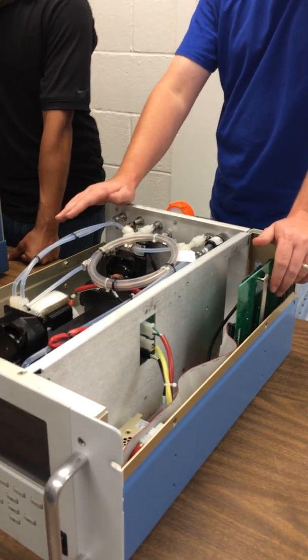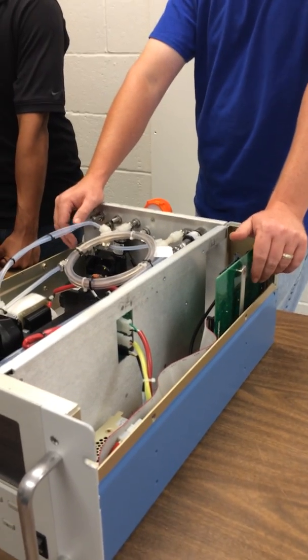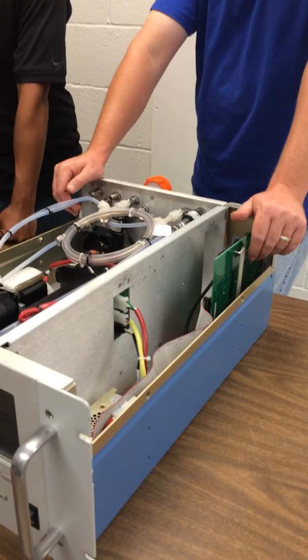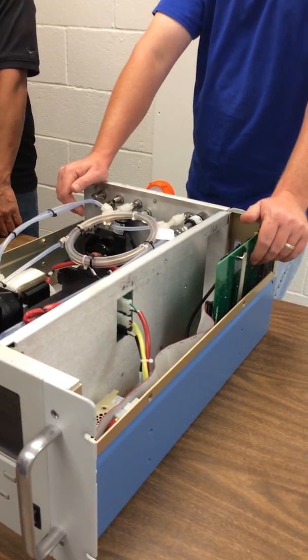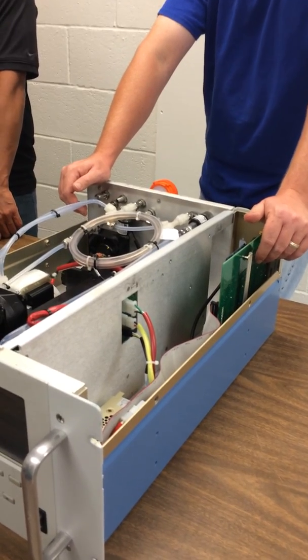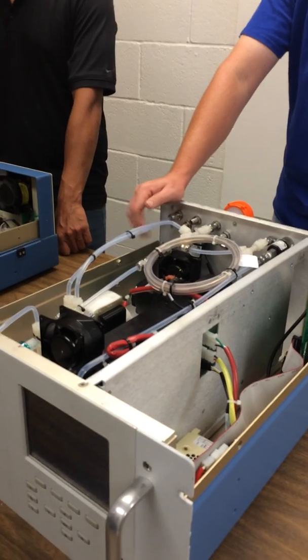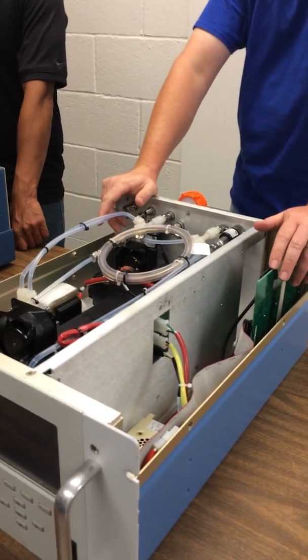I had one of these and I was playing with it one time early on just to see how bad it would go, and I let it run for about a week without resetting the zero. And it was reading 7 parts per million in the lab with a zero of 6.8 parts per million. And it would just keep walking off just forever.